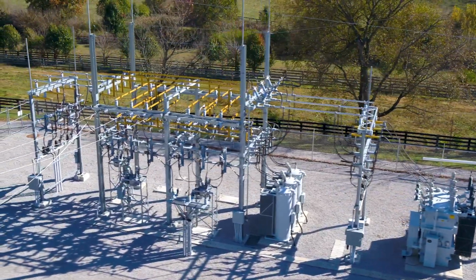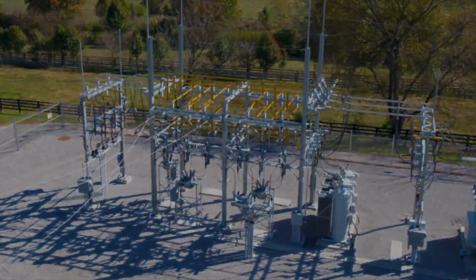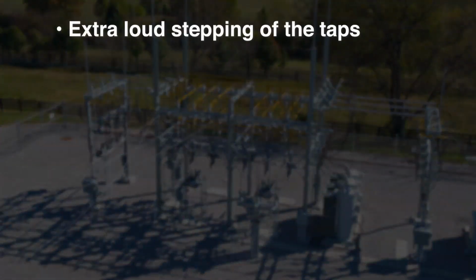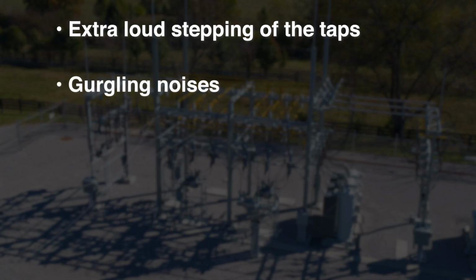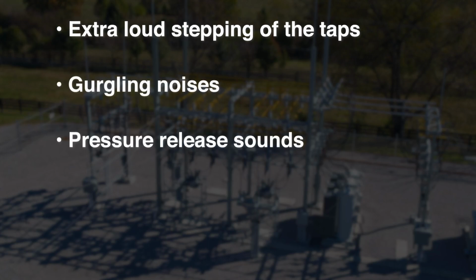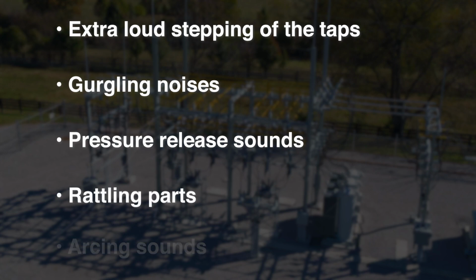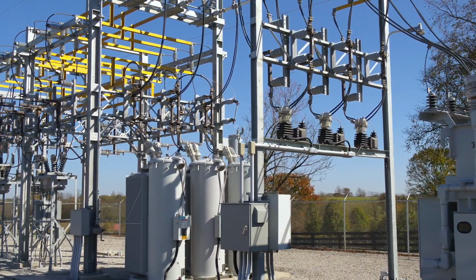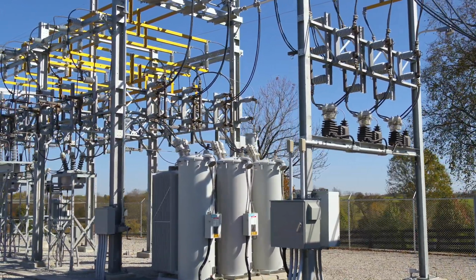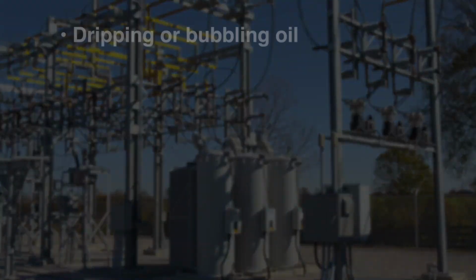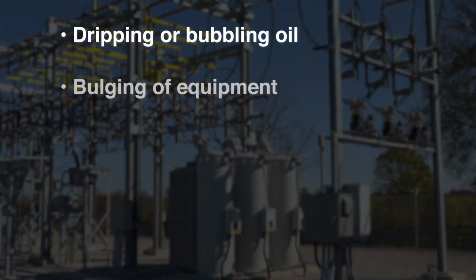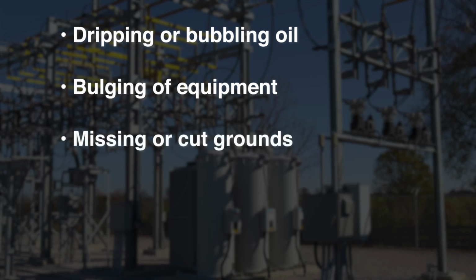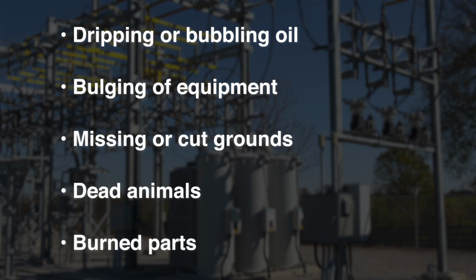There are several sounds to be concerned about if you're working near a regulator. Extra loud stepping of the taps, gurgling noises, pressure release sounds, rattling parts, arcing sounds. There are also visual signs that should be of concern. Those include dripping or bubbling oil, bulging of equipment, missing or cut grounds, dead animals, and burned parts.